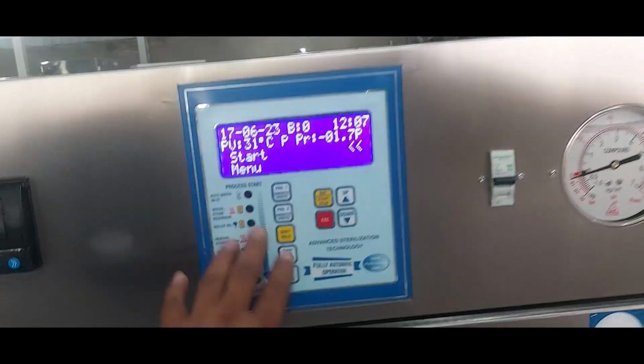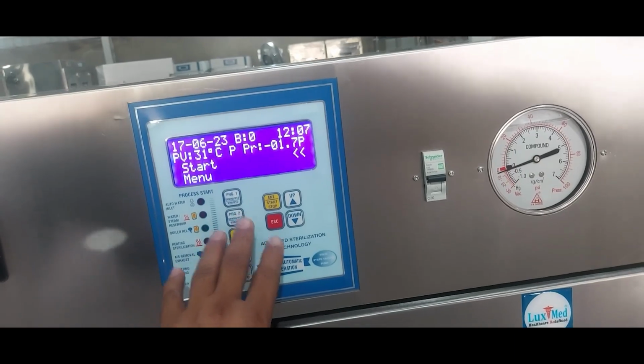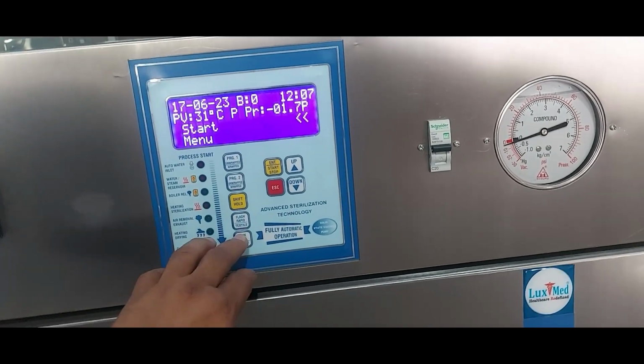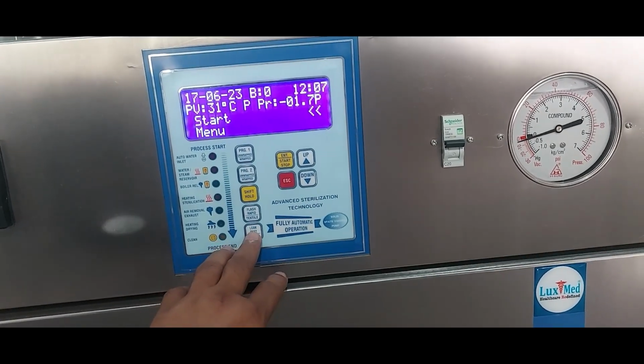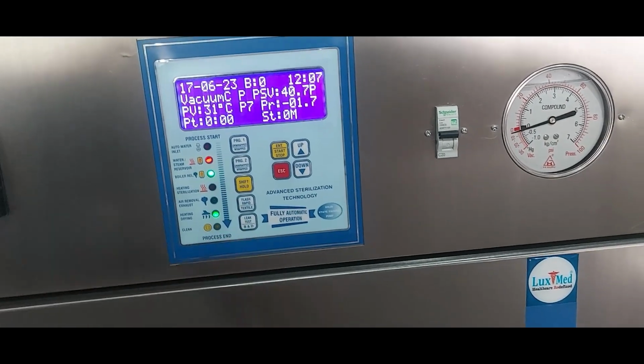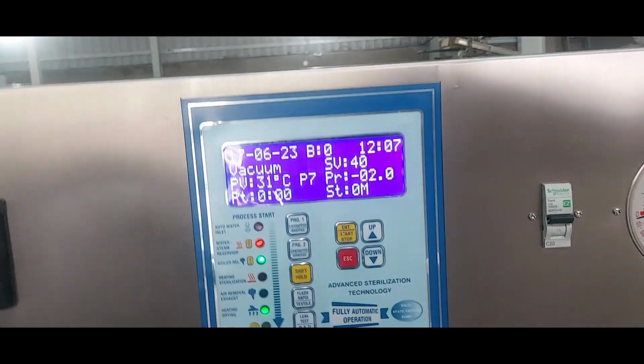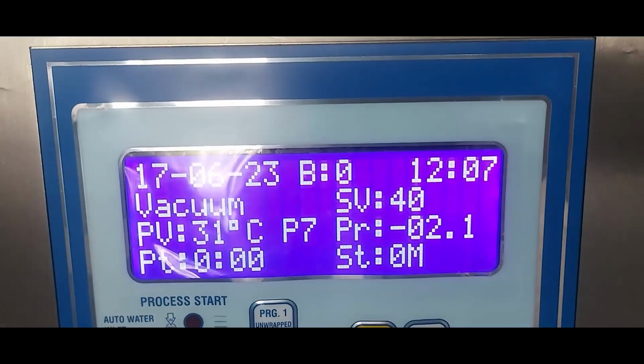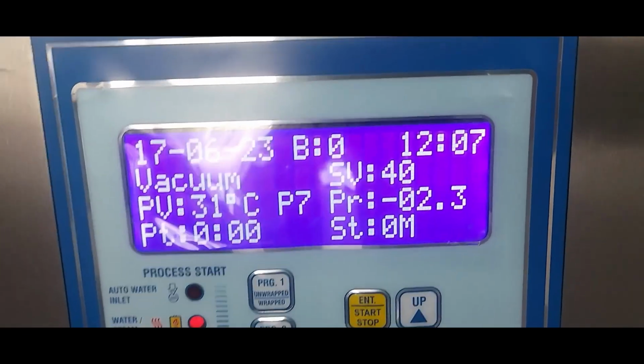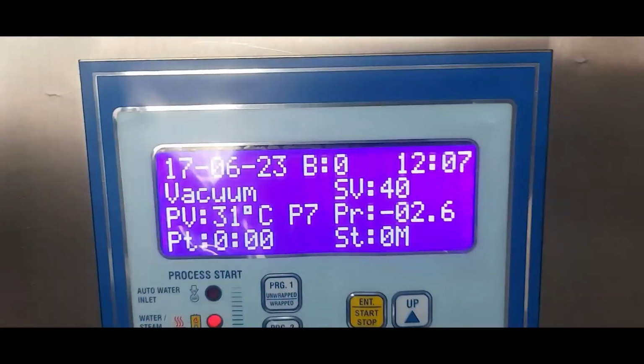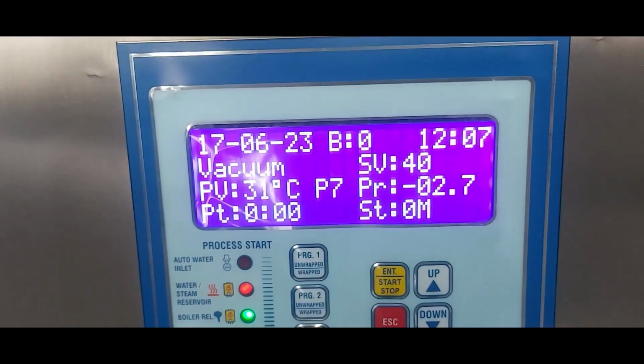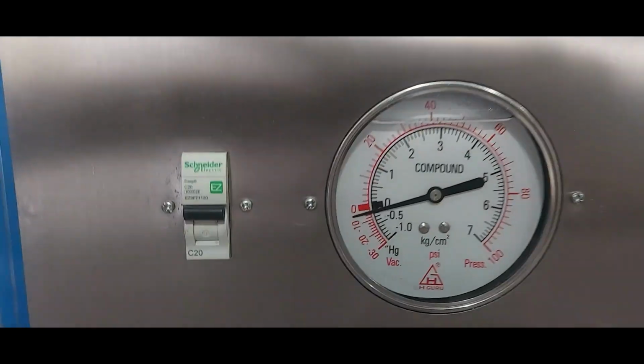Now this system has the complete internal operation. It has 8 built-in programs. Now I am running a very fast program, the leakage test program. The leakage test program has been started, and now the vacuum goes down, and it will go up to 25 pounds, and then the next process will start.